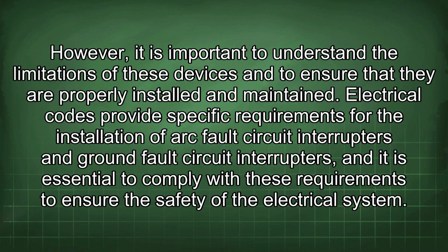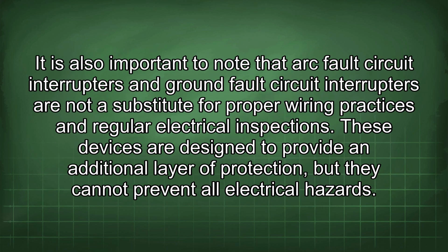However, it is important to understand the limitations of these devices and to ensure that they are properly installed and maintained. Electrical codes provide specific requirements for the installation of arc fault circuit interrupters and ground fault circuit interrupters, and it is essential to comply with these requirements to ensure the safety of the electrical system. It is also important to note that arc fault circuit interrupters and ground fault circuit interrupters are not a substitute for proper wiring practices and regular electrical inspections.